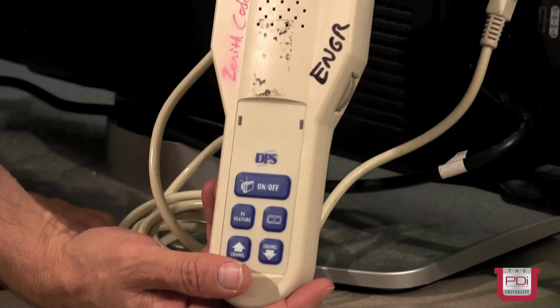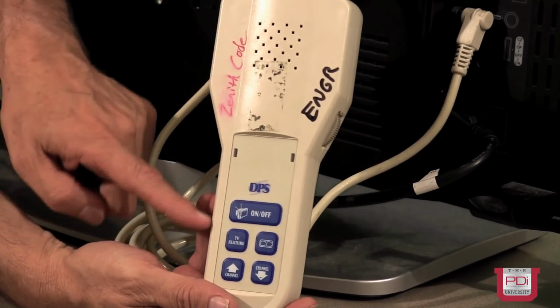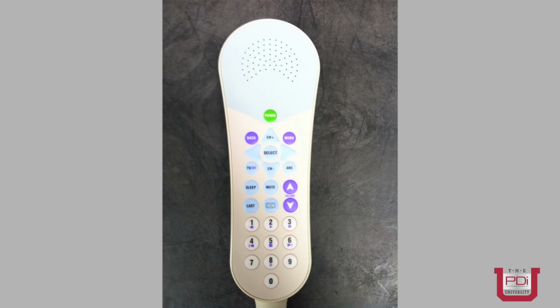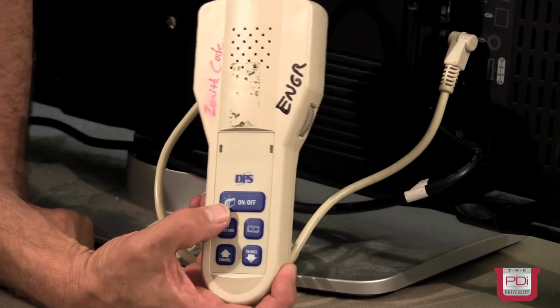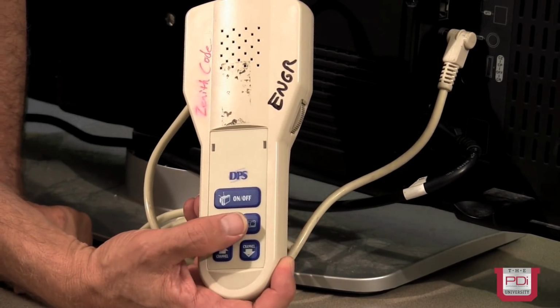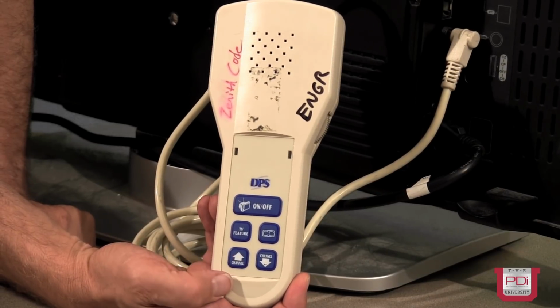Right now I've got a test pillow speaker we use here at our factory, but this is a digital pillow speaker. Some of them have, in addition to the main functions, a number pad which allows direct entry of channels for the patient. But this one's a simpler version. It has a basic on-off, channel up-down, activation of closed captioning, and also a feature button that's programmable.